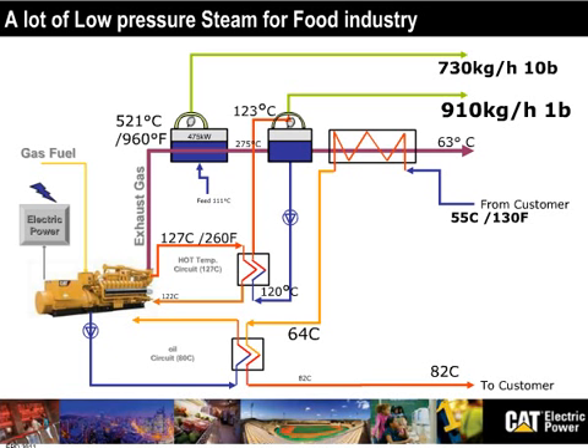This is about 3,000 pounds per hour of steam, and this is very useful for food industry, for cooking and food processing and sterilization. This has been done here in Germany and in North Africa as well on a pasta company. So steam is important for the industry. Industry loves steam, and if you use the exhaust gas only, you get some issues or challenges with your efficiency. But if you use it this way, producing high pressure and low pressure steam together and a bit of hot water, you can raise efficiency here. This example is almost 89%.